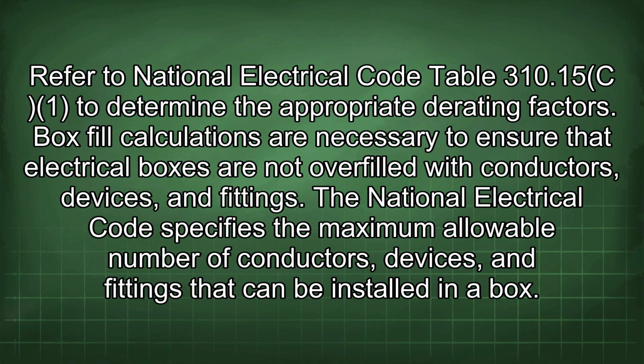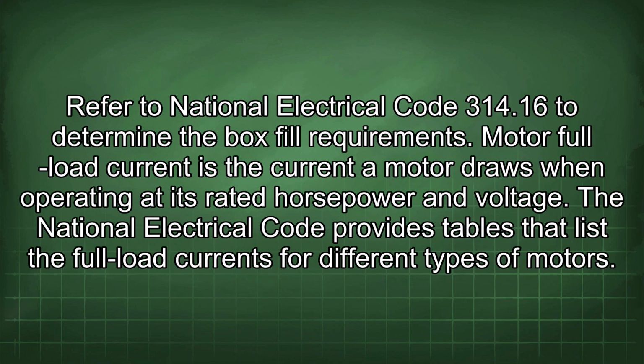Box fill calculations are necessary to ensure that electrical boxes are not overfilled with conductors, devices, and fittings. The National Electrical Code specifies the maximum allowable number of conductors, devices, and fittings that can be installed in a box. Refer to National Electrical Code 314.16 to determine the box fill requirements.